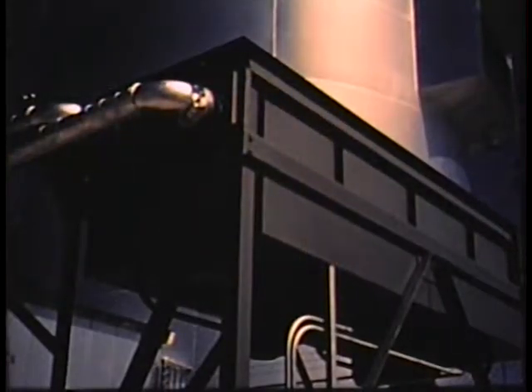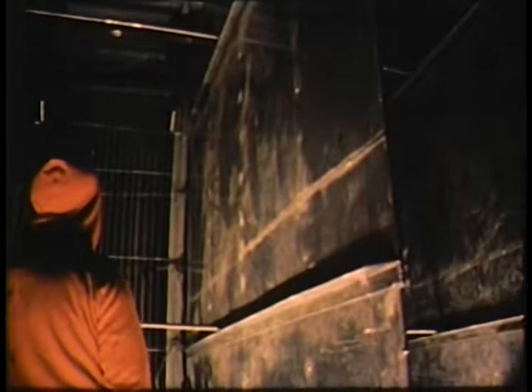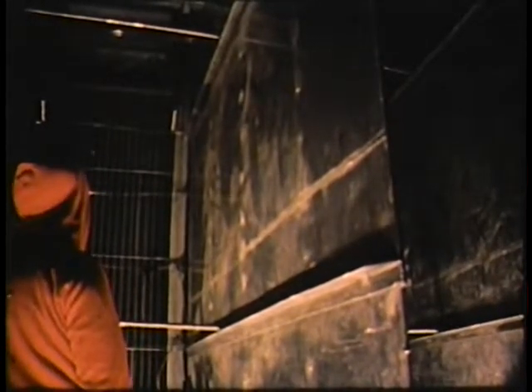In the prototype installation, an air-cooled heat dump is used to simulate a space heating load of 400 thermal kilowatts. The condensate from the space heating heat exchanger is passed to a tank where some of it is flashed to steam at a temperature of approximately 135 degrees Fahrenheit. This flashed steam is ducted to the fin tube-type steam condenser on the fan floor, as is the exhaust steam from the turbine. There, the steam is condensed by the transfer of heat through the tube walls to an airstream created by the action of a powerful fan.